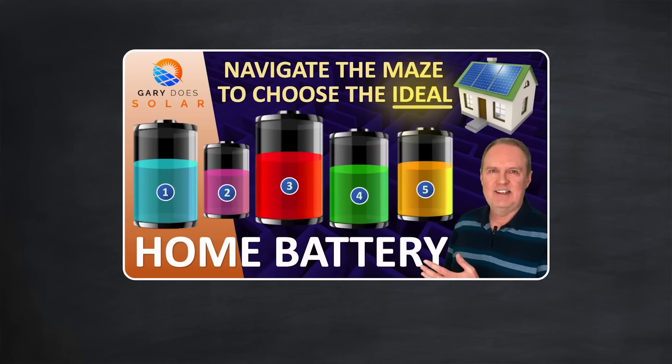What if you want to use Powerwall 3 with an existing solar installation, or wish to use micro inverters instead of a string inverter? By default, the battery inside Powerwall 3 is in a DC coupled configuration, directly linked to the built-in solar inverter. But that inverter can be disabled, allowing Powerwall 3 to simply act as an AC coupled battery — exactly how the Tesla Powerwall 2 operates. The great thing about an AC coupled battery is that it can be added to any kind of solar installation, even those with micro inverters.